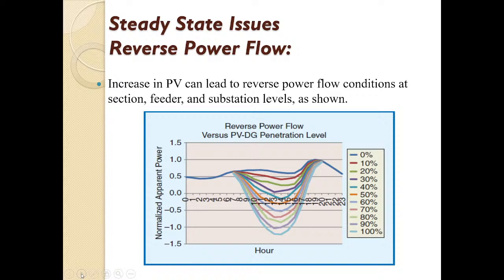Finally it will reach zero at the end, and after that, further increasing the solar photovoltaic power, it will enter the negative region, meaning it is feeding power in the opposite direction. When power feeding is in the opposite direction, there will be multiple protection issues and heating elements coming into picture, so reverse power flow in a big way is normally not advisable. Going from the blue curve to the violet curve, you will be having a higher and higher ramp rate.